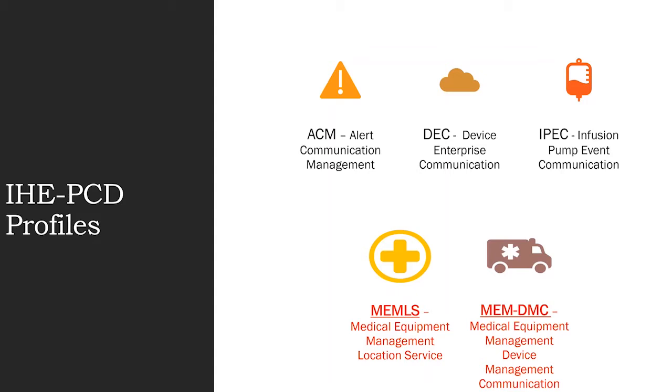The bottom 2 profiles are both in the MEM world: the MEMLS, which is the location services, and then the MEM DMC, which is medical equipment management, device to management communication. And these are where all the observations, the different statuses and triggers, go out to open work orders. And EQ2 developed this protocol.